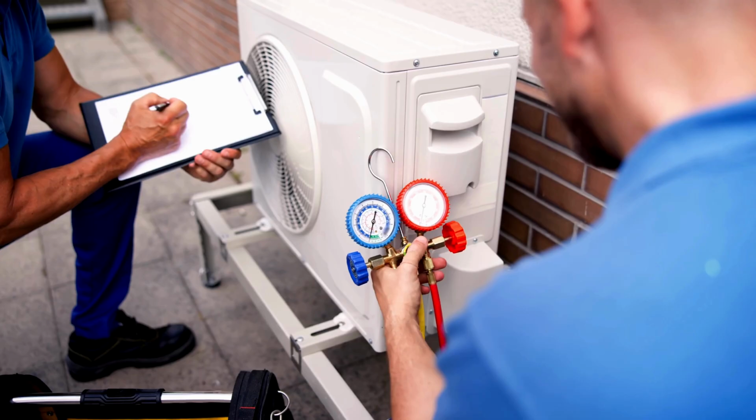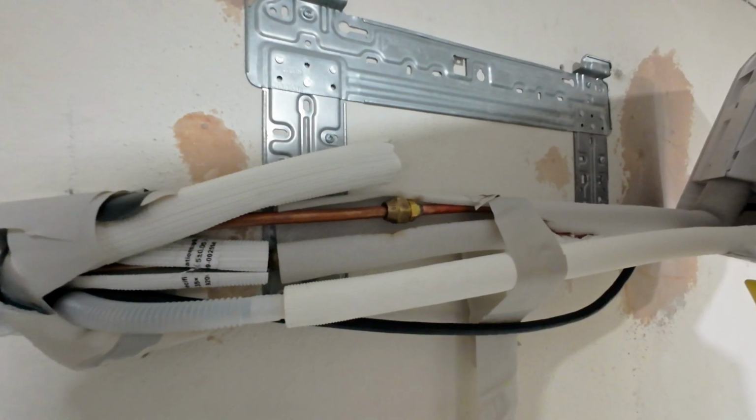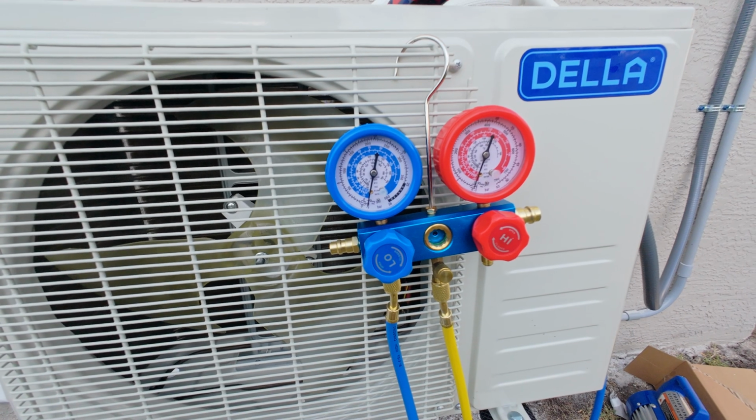At this point, I was so frustrated. I was like, why didn't I get a licensed HVAC contractor to do this? But then again, I remembered the cost. So I calmed myself down and started to think. Eventually, I went back and moved the indoor unit off the wall, and to our surprise, there was a hiss at the connection, and that's where the leak was coming from. So I tightened the connections and the vacuum improved, but it was still not perfect.